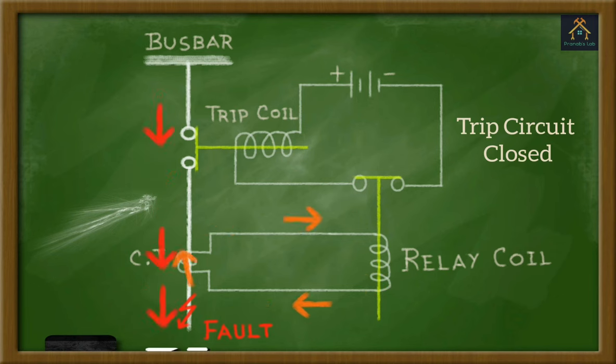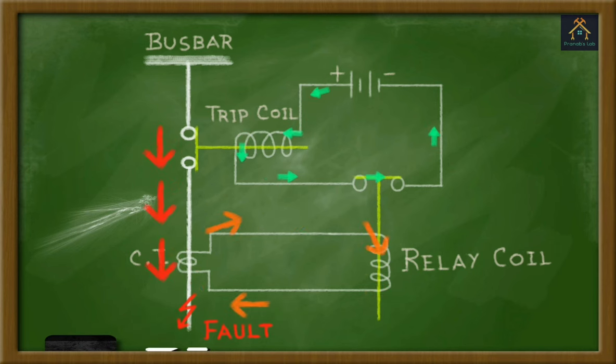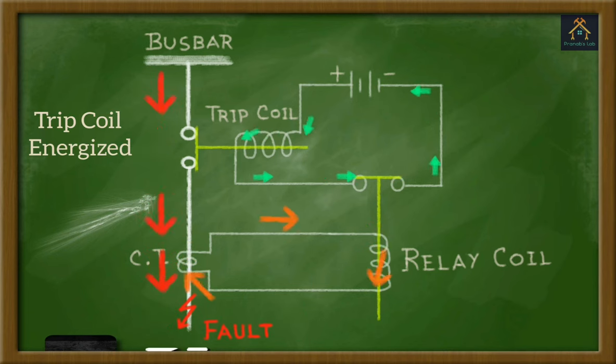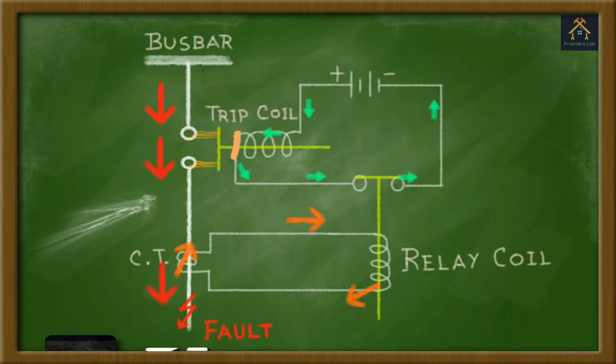The plunger will close the trip circuit and a current will be flowed through the trip coil. By flowing normal current through the trip coil, it gets energized. As a result, the trip coil plunger will be attracted. And finally, the circuit is opened with the opening of the circuit breaker.